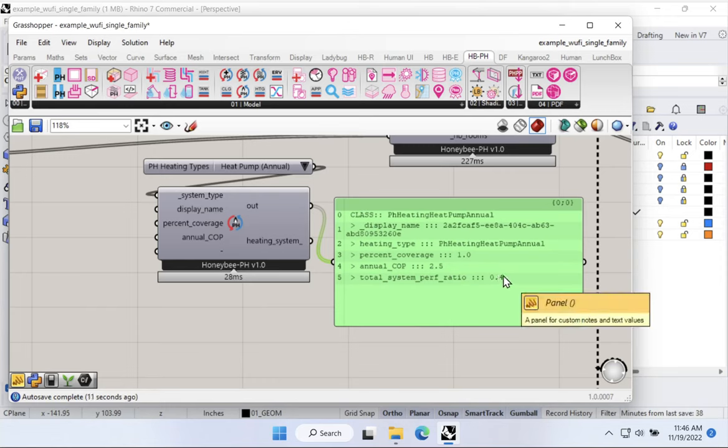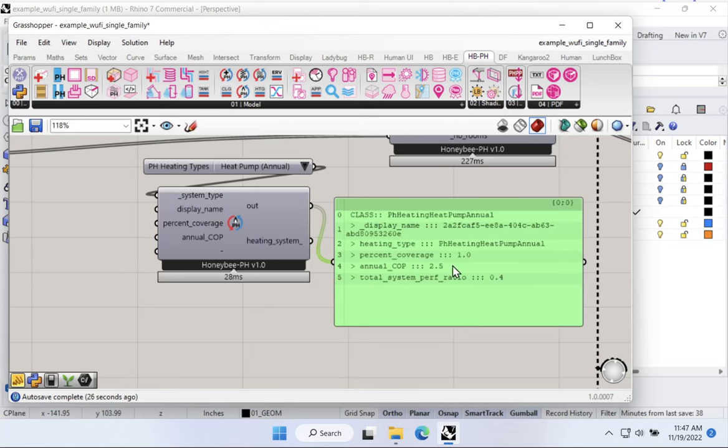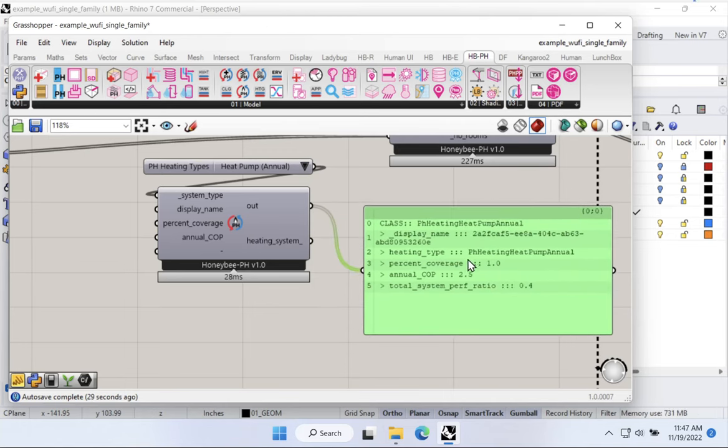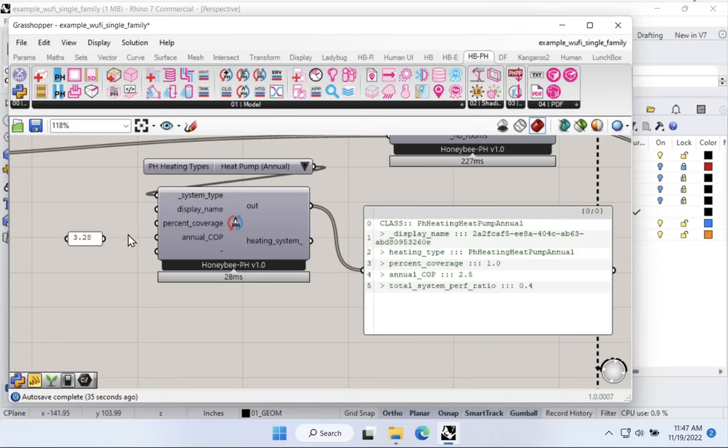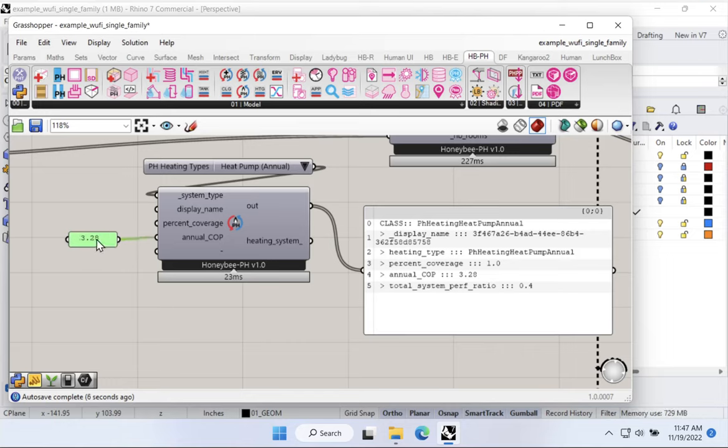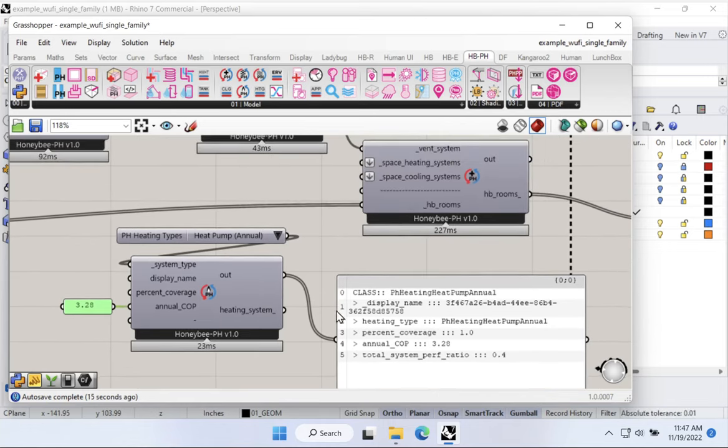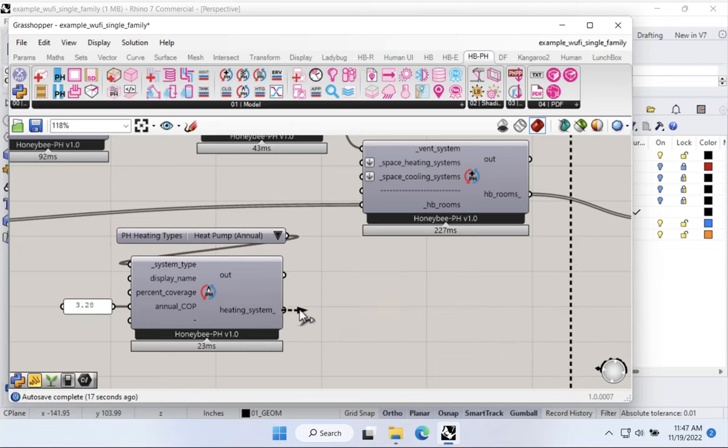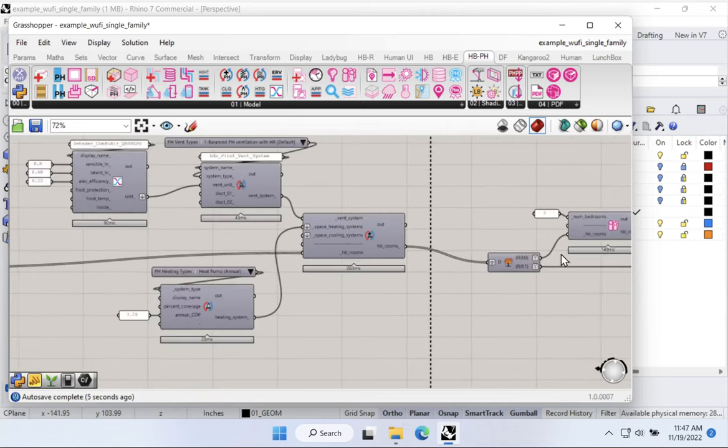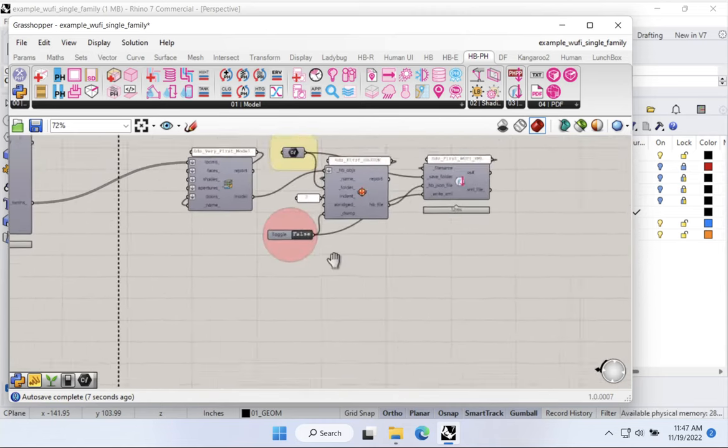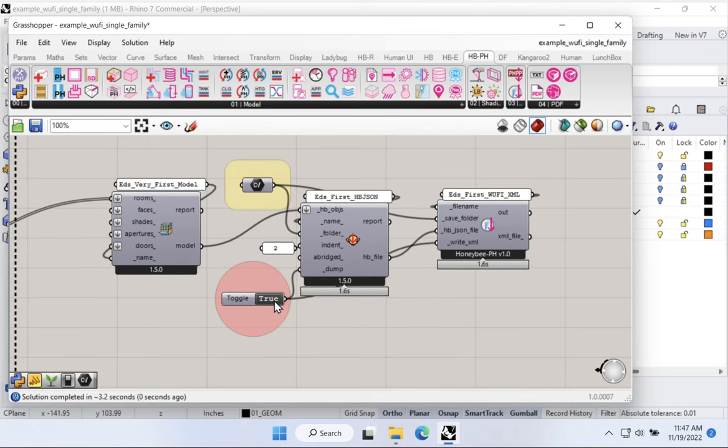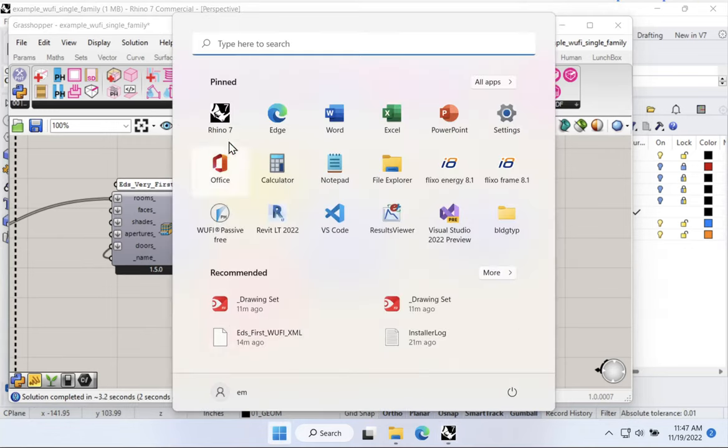Let's take a look at the default output of this component. The default output of this component is a heat pump with a COP of 2.5, total system performance ratio of 0.4. That's not great. It's 2022 as I'm recording this. We can get better equipment than this, but this is probably a good middle-of-the-road kind of conservative estimate for the annual COP performance, heating system performance, of a piece of heat pump equipment in a cold climate. So fine. We could just kind of leave it at that. If we wanted to, we could always come in here and we could set this to 3.28 or whatever, whatever the number is that we think is correct. And notice that number will track through. I'm not going to talk about where these numbers come from. But once you know what the right COP number for your equipment is, you can input it here. And then all you have to do is take the heating system and apply the heating system to our honeybee spaces or our honeybee rooms. And when we do that, let's come over to our export here. We will export our project.